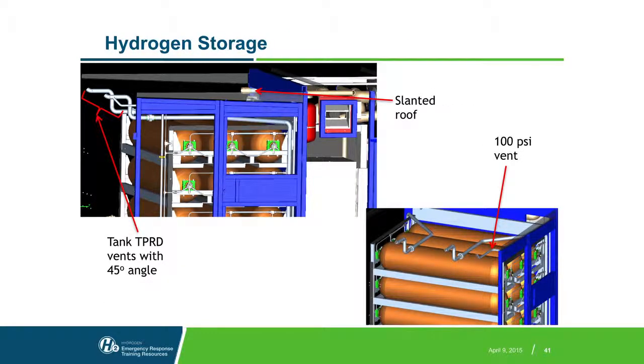So this is a computer rendering of what they look like. Again, 15 tanks in the storage unit. These are the high pressure vents. There are those thermally activated PRDs in the ends of both tanks, as well as the solenoid valves and other equipment for regulating pressure and so forth. This is at the end of the tank at the top, with a 45-degree angle to facilitate venting up and away, as well as a 45-degree angled roof, because if you did have a leak, the hydrogen would want to migrate to the highest point and leak out, being so light.